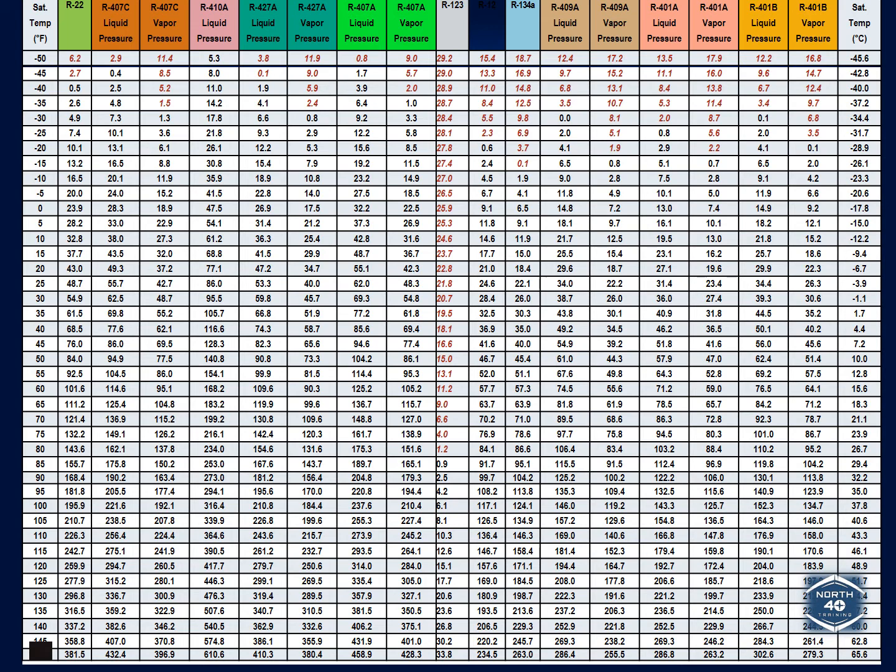It's above freezing. It's not grossly above there, but really what you're trying to do is figure out with a PT chart, the most valuable lesson that you get from the PT chart is how those pressures and temperatures correlate to each other and how much different it is, right? 410A was operating at 10 degrees, for goodness sakes, when it comes to the 60 psi and how that corresponded to temperature.